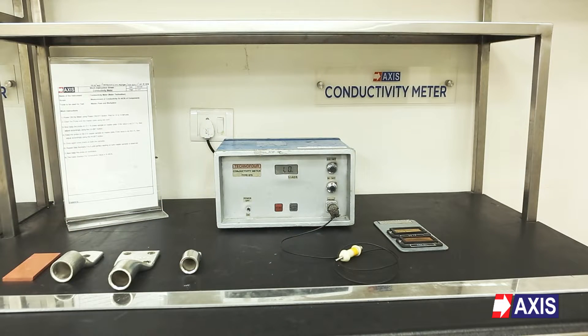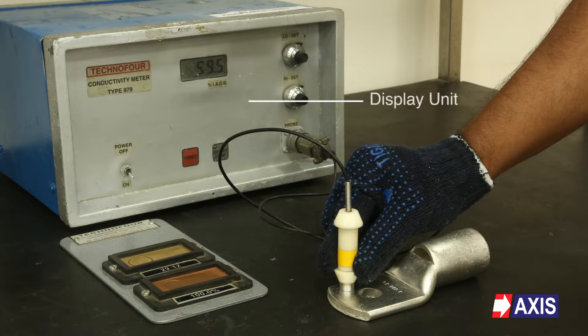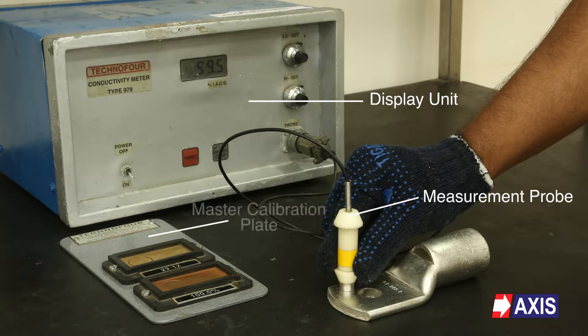Equipment used and their applications. To measure the electrical conductivity of a metallic item, we use three tools: Number one, display unit. Number two, measurement probe used to measure the conductivity of the metals. Number three, master calibration plate.